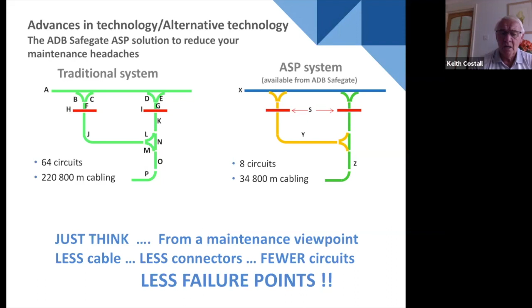But if we go to the ASP system and do these combinations, we can get that same configuration down to around 8 circuits and just under 35,000 meters. That's one heck of a saving. Less cable, less connectors, fewer circuits. Overall, it's commercially attractive, maintenance attractive, and simpler to install.